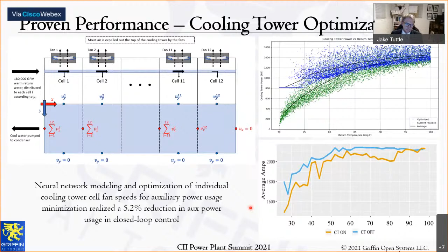Beyond that, at this same site, we were able to do cooling tower optimization in this application, with the objective of reducing auxiliary power usage. You see in this example, by adjusting the fan speeds of individual cells in this cooling tower, this is a forced draft cooling tower, we reduce auxiliary power usage by over 5%.